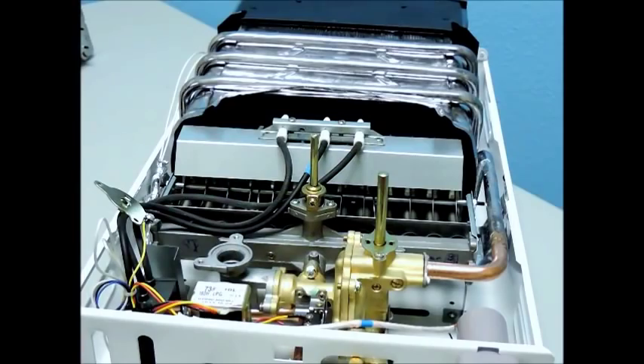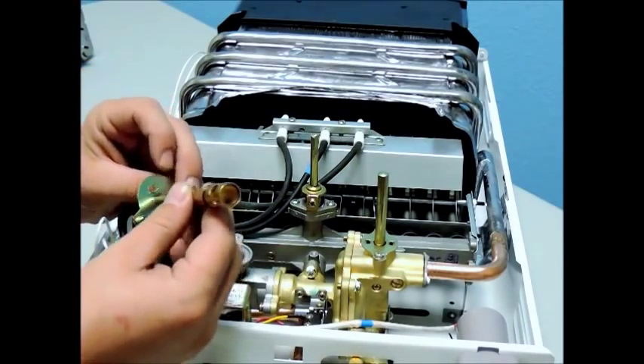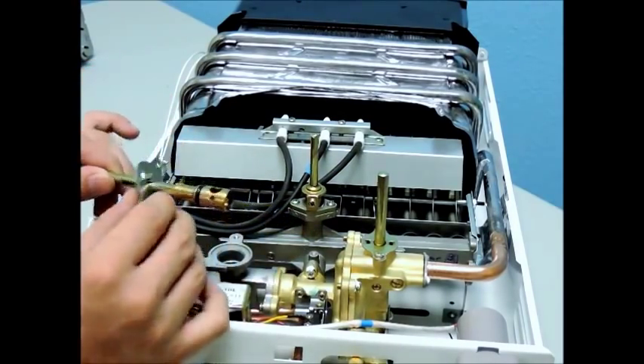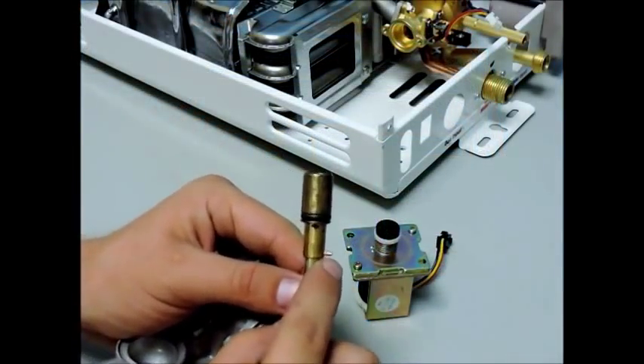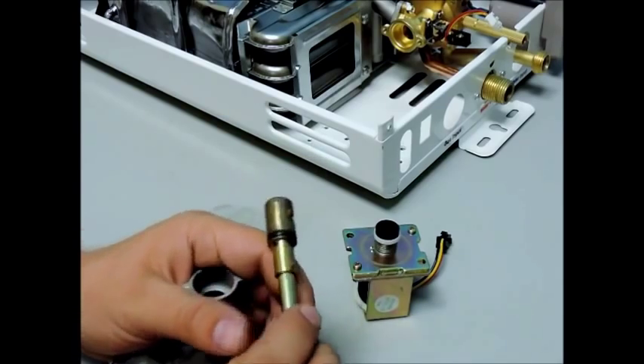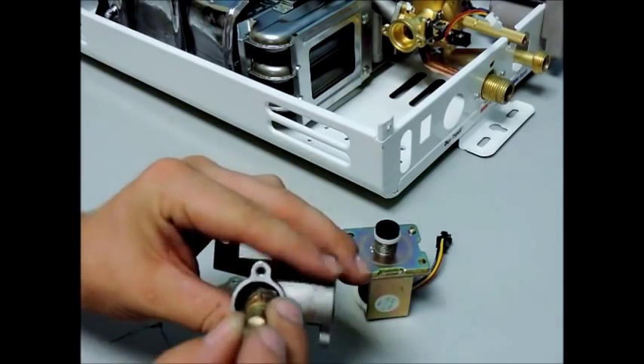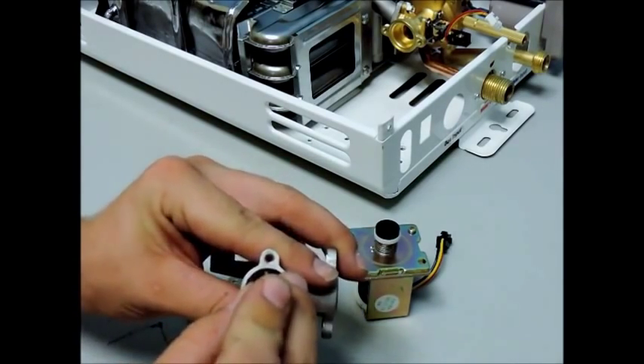Next, slide the gas valve retaining plate onto the stem and insert the stem back into the gas valve with the guide pin positioned at the 12 o'clock. Reinsert the two screws that secure the retaining plate to the gas valve.